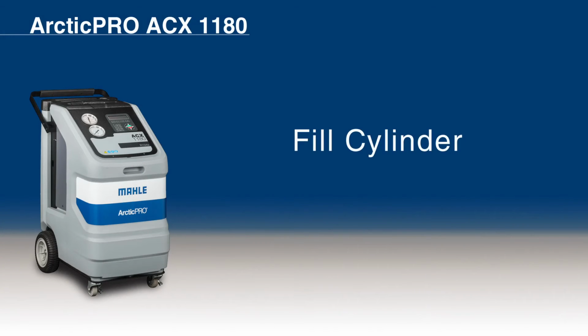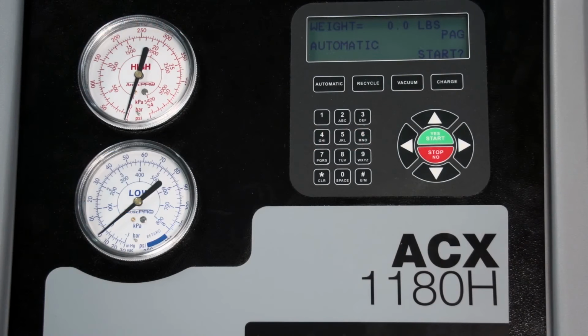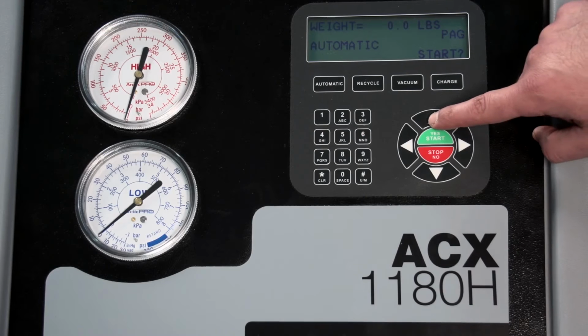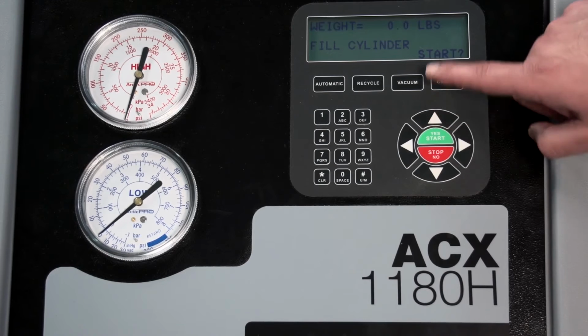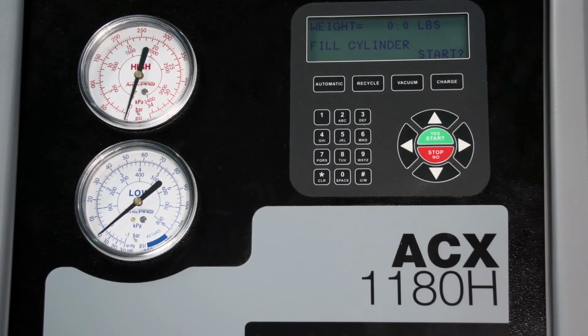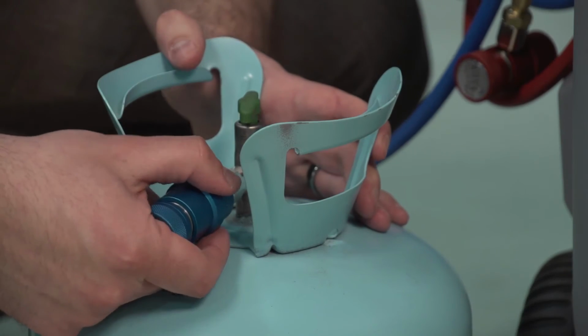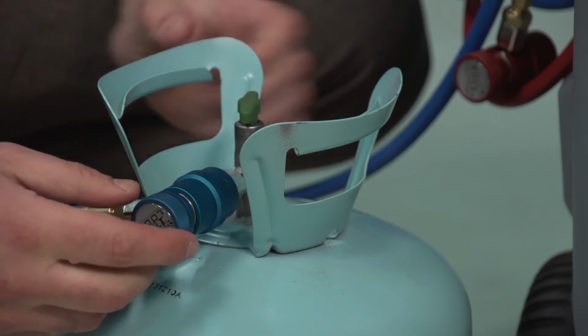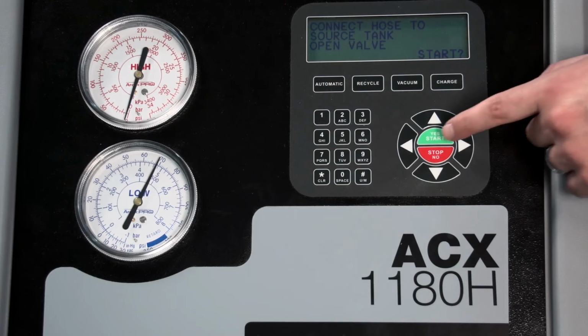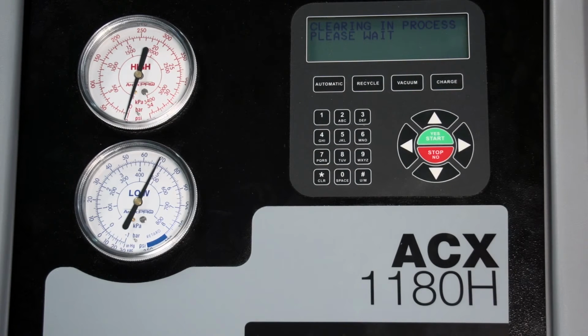Fill the internal cylinder. To fill the ACX1180 internal cylinder, press the up arrow until the display reads Fill Cylinder. Press the Yes key. The screen will display Connect the hose to the source tank and open the valve. Once you've done that, you can select Start. The screen will display Clearing in Process. This takes between 30 and 60 seconds to complete.